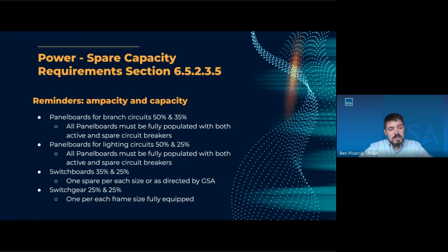So switchboards and switchgear are a little bit different. The capacities are a little less because they're larger pieces of equipment. For the switchboards, it's one spare per each size circuit breaker. Typically a switchboard is going to be feeding mechanical equipment or something larger that uses a 60 amp, 80 amp breaker, 40 amp, whatever it may be.